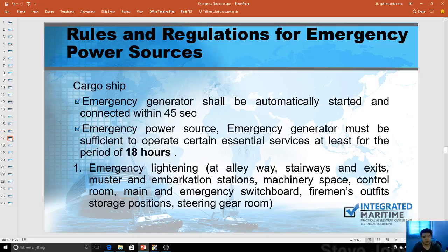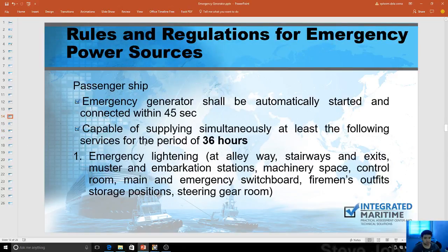On cargo ships, it's the same — 45 seconds for auto-start. But the essential service time is lower, at 18 hours, compared to 36 hours for a passenger vessel. The same emergency lighting requirements apply. The key difference between a passenger vessel and a cargo vessel is just the time: passenger vessel is 36 hours, cargo vessel is 18 hours.